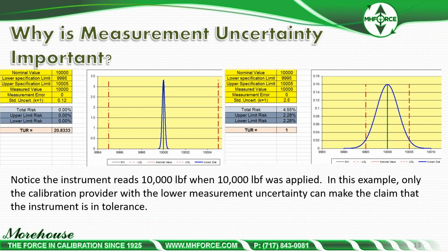so they're going to get larger. If we look at this graphically, we can look at 10,000 pounds. Here it is graphically. One, you see the repeatability and you see the CMCs, you see a very, very steep curve. And the other one, you see a less steep curve. And all this really is, is we're changing the uncertainties of the lab where this was sent for calibration. Both labs have the same measured value.